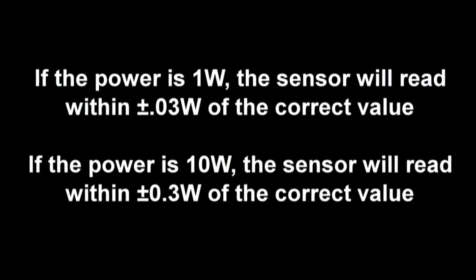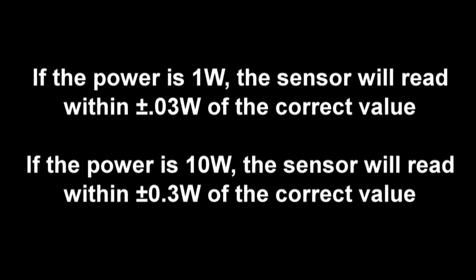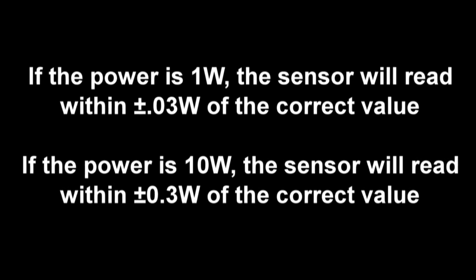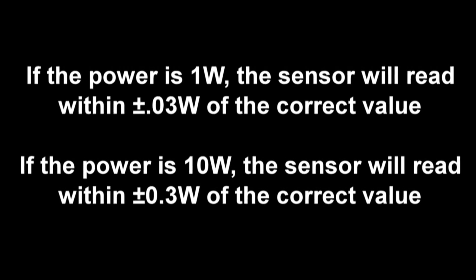This specification means that the sensor will read within plus or minus 3% of the correct value at each power. Thus if the sensor is calibrated with a centered beam at 532 nanometer at 1 watt, the sensor will read within plus or minus 0.03 watts of the correct value. If it's 10 watts, it'll read within plus or minus 0.3 watts.